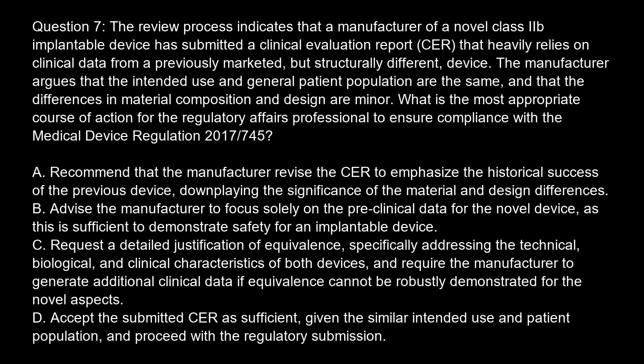Option A. Recommend that the manufacturer revise the CER to emphasize the historical success of the previous device, downplaying the significance of the material and design differences. Option B. Advise the manufacturer to focus solely on the preclinical data for the novel device, as this is sufficient to demonstrate safety for an implantable device. Option C. Request a detailed justification of equivalence, specifically addressing the technical, biological, and clinical characteristics of both devices, and require the manufacturer to generate additional clinical data if equivalence cannot be robustly demonstrated for the novel aspects. Option D. Accept the submitted CER as sufficient, given the similar intended use and patient population, and proceed with the regulatory submission.